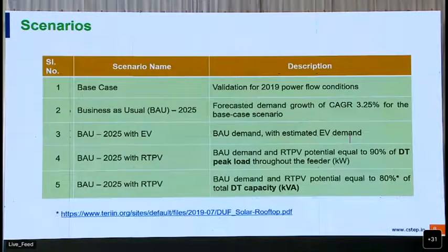So for this particular feeder, we have carried out around 5 scenarios. The first scenario is the base case scenario. There we have given the existing loading of the DTs, and we have also validated this feeder to check whether the loading has been considered properly for the particular instant. So this is basically for validation purposes. We have considered the existing values for 2019. And for the rest, we have carried out the studies for 2025.